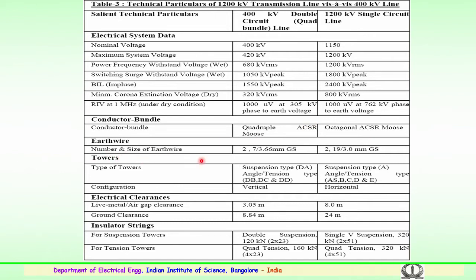For earth wires: 400 kV typically uses 2 earth wires with 7 strands of 3.6 mm dia galvanized steel. For 1200 kV, 2 earth wires with 19 strands of 3 mm dia galvanized steel are used. In terms of tower types: for 400 kV, DA is used for suspension; DB, DC, and DD are used for tension. For 1200 kV, tower type A is used for suspension, and types A, S, B, C, D, and E are employed for tension. Configuration: 400 kV uses vertical configuration; 1200 kV uses horizontal configuration.